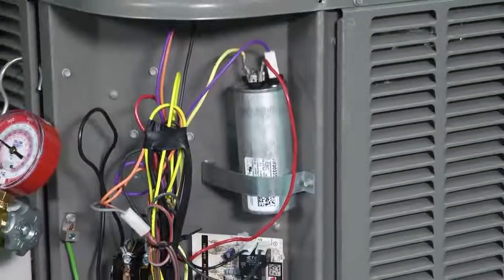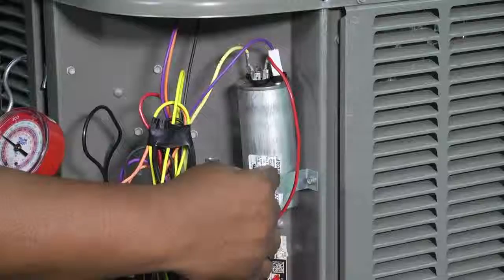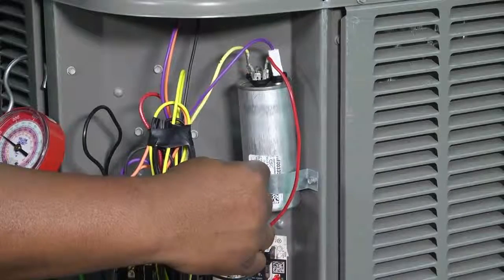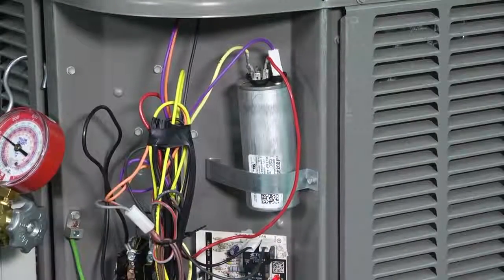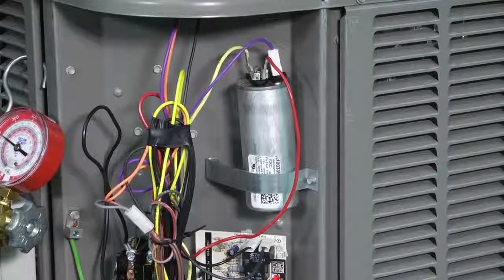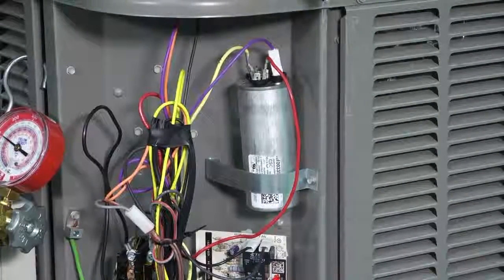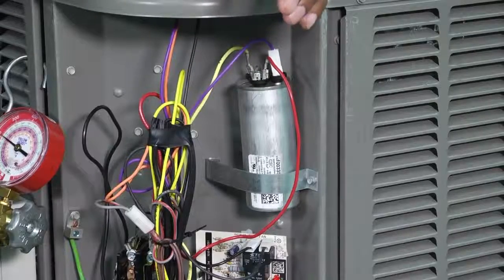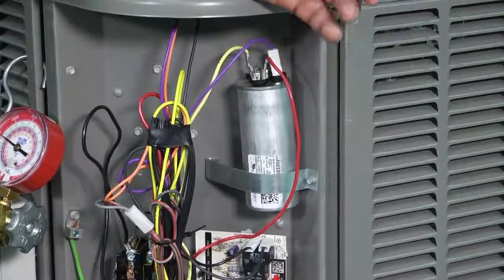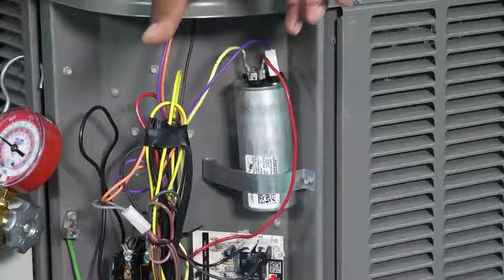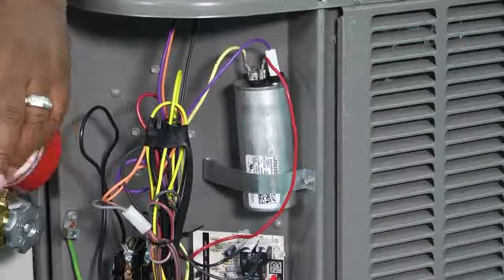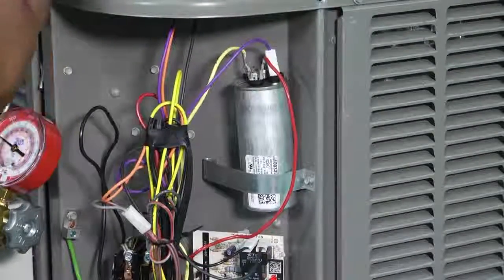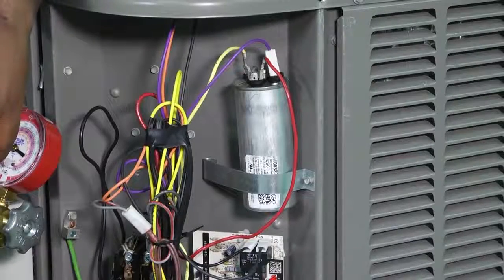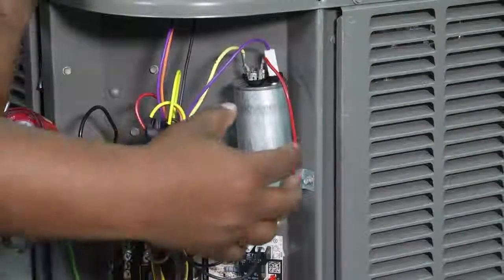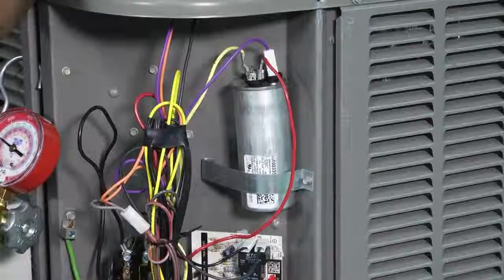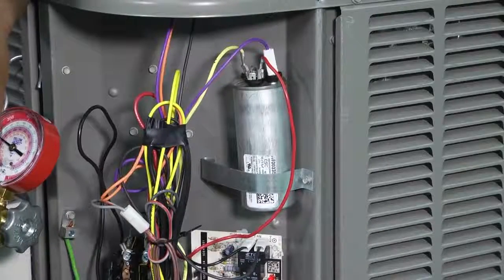Now, once you do that, the great thing about these capacitors is they have a level here recommended by the manufacturer as when the manufacturer says this capacitor is good or bad. Sometimes you can have a capacitor that is outside of manufacturer specifications, but still operational. And there's a huge skill set here that's needed for the technician to be able to have a conversation with the homeowner as it relates to an operational capacitor that's testing below manufacturer specifications.